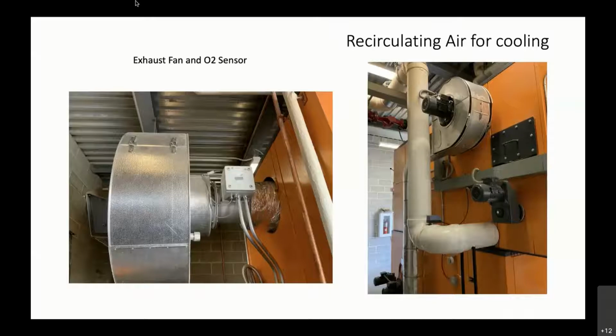On the left-hand side, you have the flue gas fan and the lambda sensors, so the O2 sensors. So the boiler really does drive to about, on the dry chips, targets about 10% oxygen. And in general, achieves that quite easily. It's not a problem to run at 8 or 10% oxygen. Depending on your moisture content, you really tune that in the beginning and then you set that.